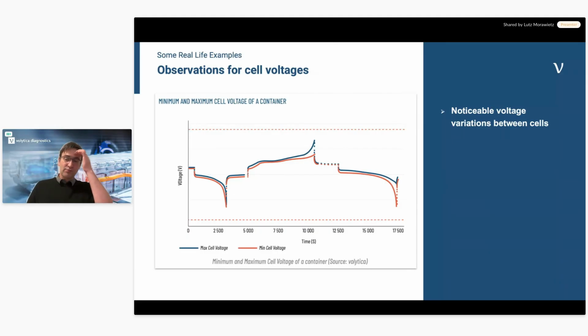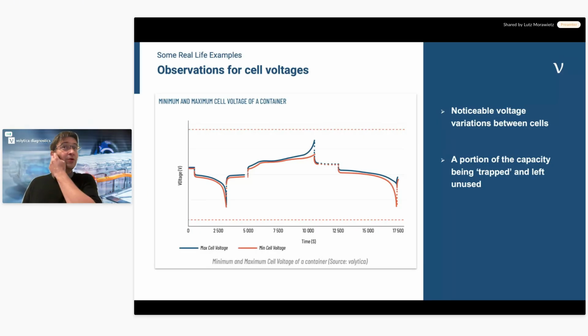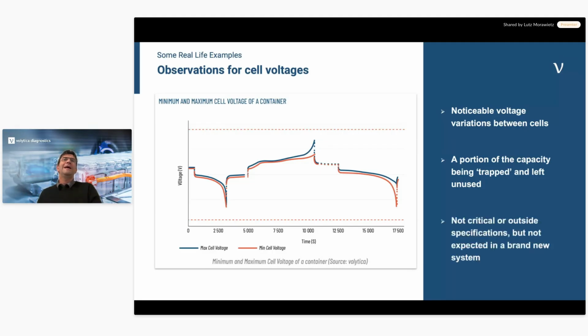If you just looked at the report from your manufacturer, they would say everything is safe with the system, and they are not lying - no voltage limit is breached. But if cells inside a battery are disbalanced, this means some of the capacity is trapped. If the orange cell is empty, the blue cell cannot be discharged anymore. So the orange cell limits the capacity at the lower end, and the blue cell at the upper end. You don't have enough usable energy - if the battery were more balanced, you could use more of the available energy inside. It's not critical or outside specification, but it's not expected in a brand new system.